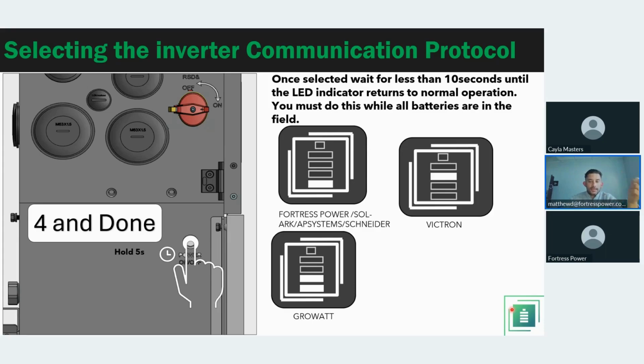And you get to select the protocol. So the default protocol that comes integrated already in the battery is Fortress Power by default. But if you wanted to use other inverter manufacturers, that would be the way to do it. So you hold it 5 seconds, release, it's going to blink, and it's going to let you know in what status it is.